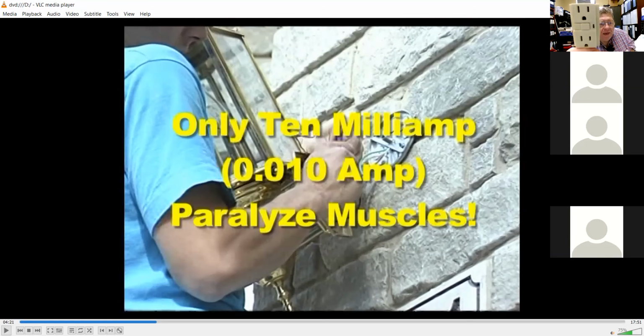What it does is it detects if you have missing current or leakage current. If you're at home and you plug a hair dryer into this in your bathroom, the little narrow slot on this side is actually the hot wire. As y'all saw in your lab that you were wiring up Tuesday, the narrow slot is hot. Now, if you plug a hair dryer into this, it draws so many amps out of that hot, through the heater element in your hair dryer, and then it comes back on the neutral.